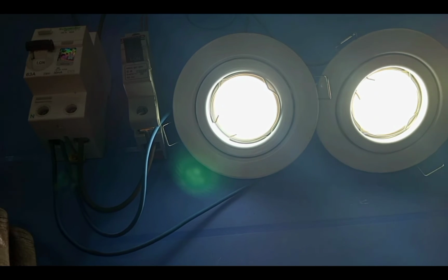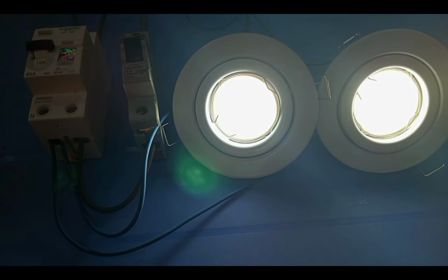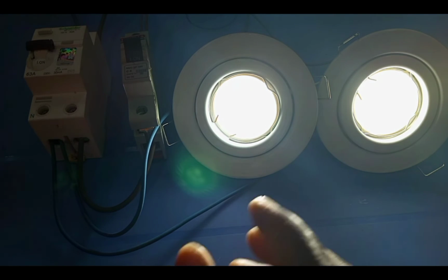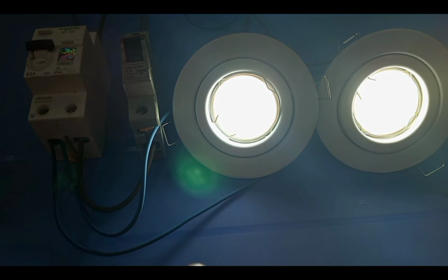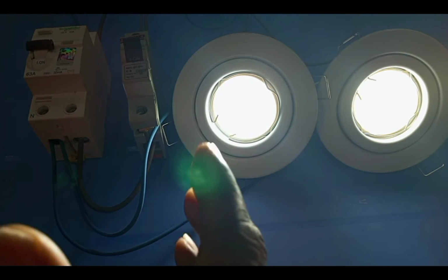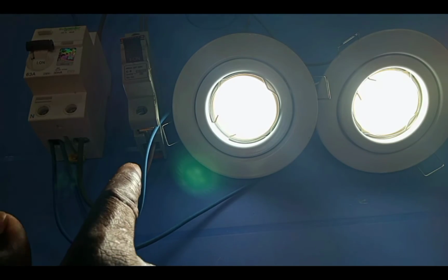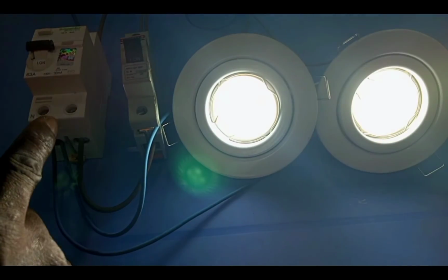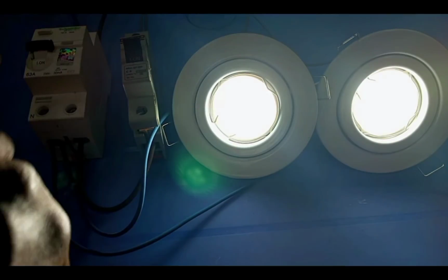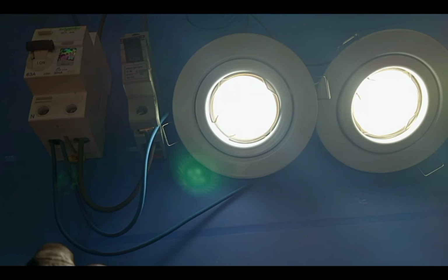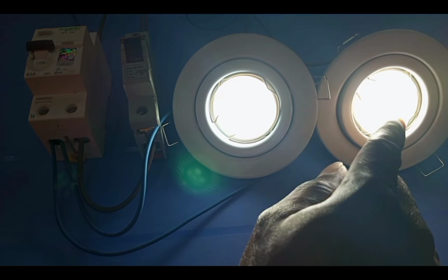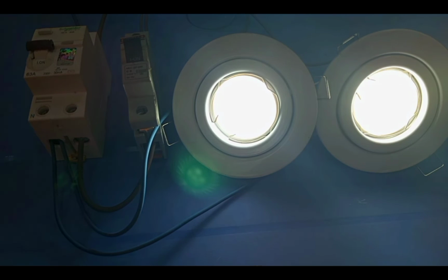All right. Now, imbalance, imbalance, imbalance. I'm going to practically show you what I mean when I say imbalance in the system. All right. So I'm going to remove one of these lamps, and at this time, I'll connect it in such a way that the live output to the lamps will all be connected through the RCD, through the breaker. So I'll not change anything about the live wires, but I'll remove the neutral wire that is going to the second lamp that I added, and then I'll connect it to a different neutral source.